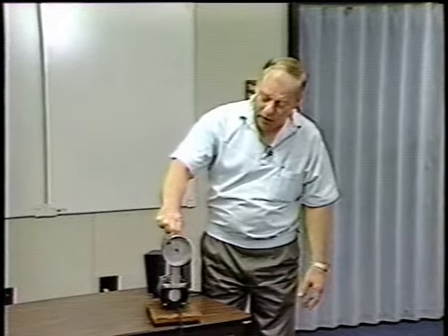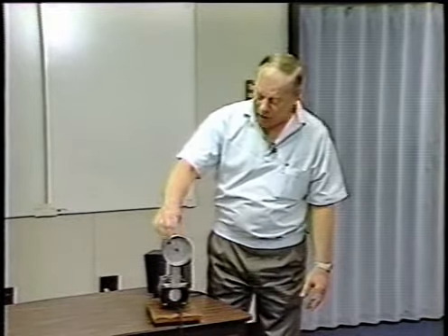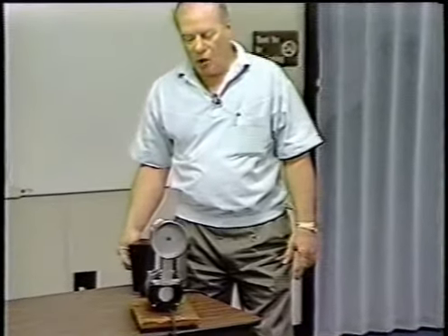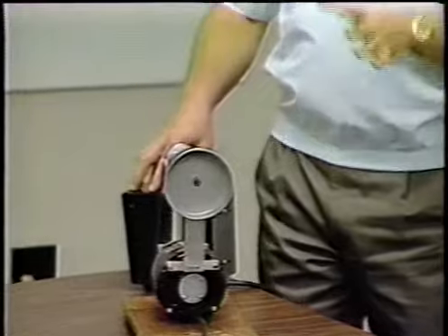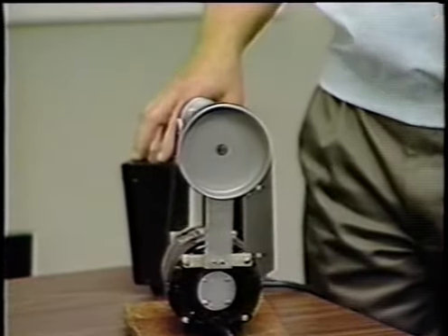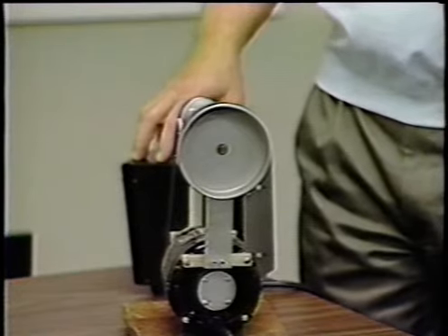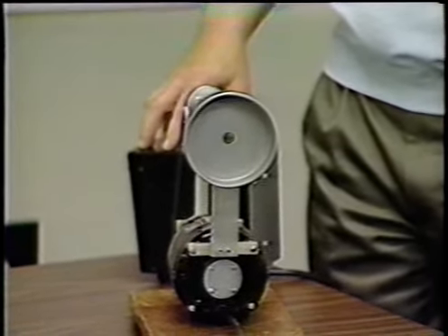In the axial direction, we have a little bit different stiffness there, so again, we've got a different natural frequency in the axial direction. I'm going to start this up to demonstrate resonance, and essentially all resonance is a situation where you have an exciting force frequency, perhaps an unbalance, cavitation problem, or hydraulic pulsation problem, and that happens to occur at the same frequency as an element natural frequency.